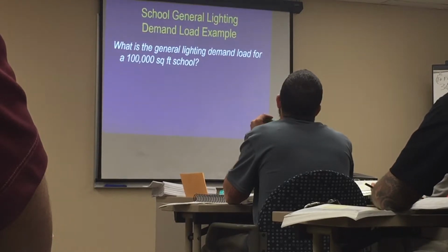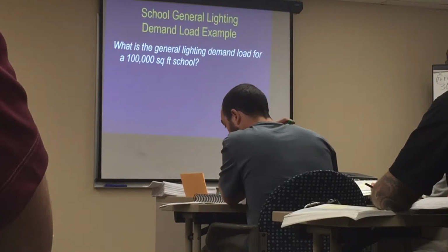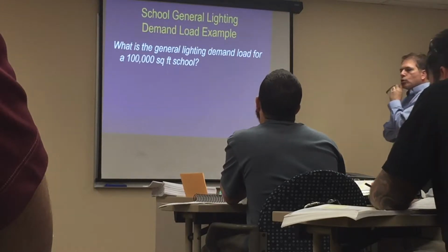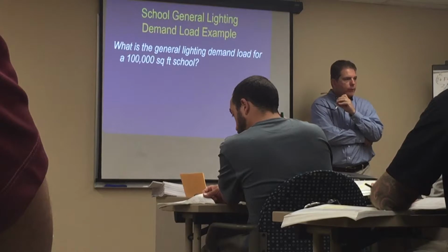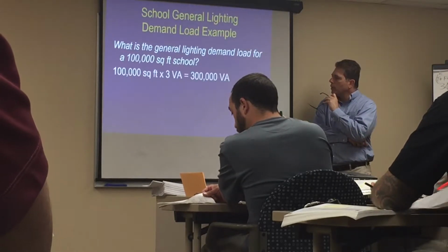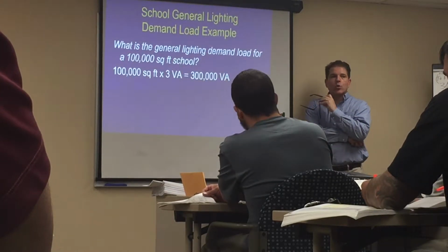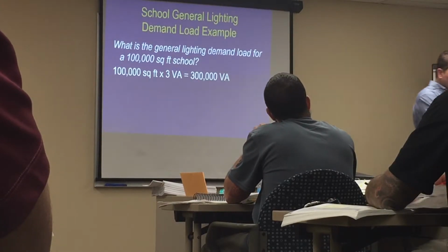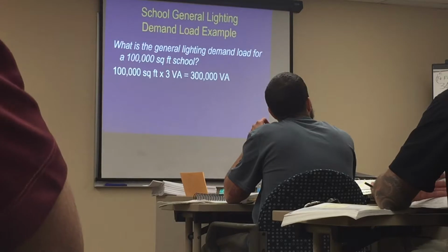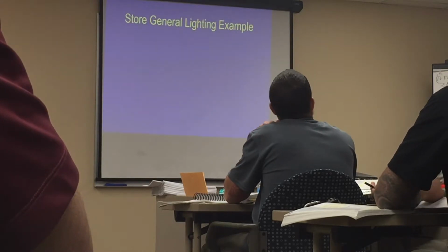How about a school? What's the general lighting load for a school? 3 watts a square foot? Yeah, okay, 3 watts a square foot. Is there a demand for a school? No. I wouldn't think so. Makes sense if there was. Yep.